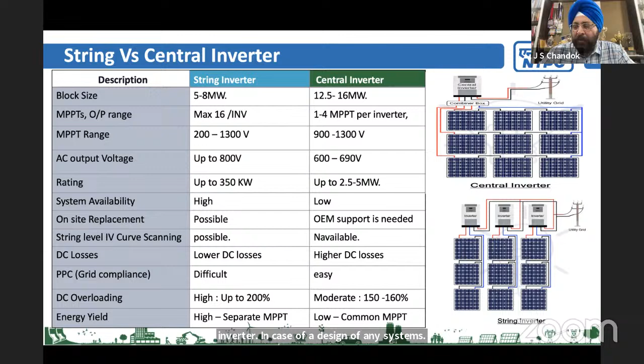This is a very important concept because when we install a solar plant, it doesn't always receive 1000 watt per meter square. Sometimes it receives 200 watt per meter square, sometimes 400 watt per meter square, and only for a few hours, half an hour or an hour, it gets close to 1000 watt per meter square. So when we design the complete system assuming 1000 watt per meter square, but we are not getting that radiation all the time, it is always advisable to install more panels with the same inverter. For example, with a 1 megawatt inverter, you can install 1.5 megawatt of solar modules.